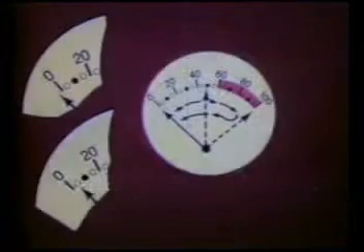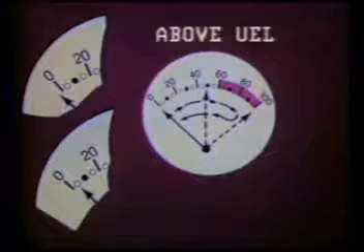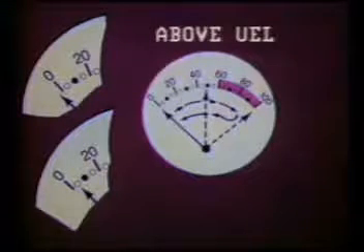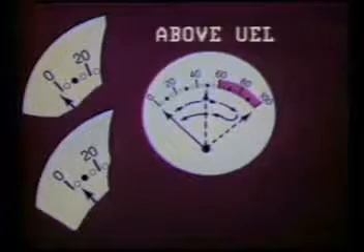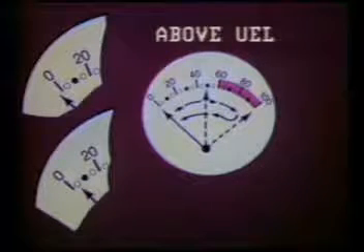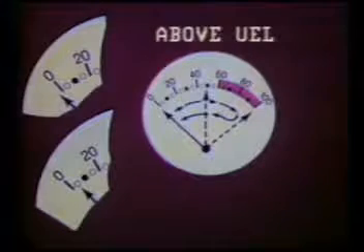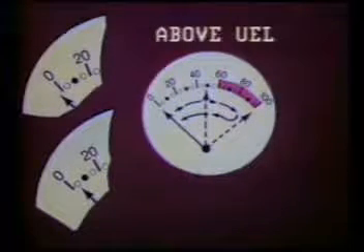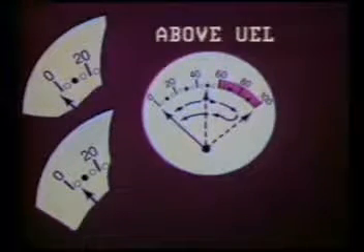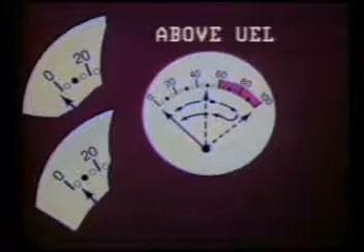Another situation that may occur with a sample in the rich range is that the needle will go upscale and come down to a point slightly above or slightly below 0. This depends on how well the gas in the sample conducts heat. Because gases conduct heat in different degrees, there may be a shift in the 0 even though there's no combustion.